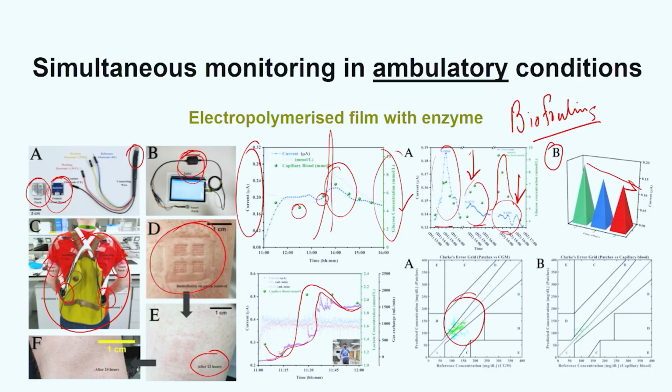The reading where you need to be very, very careful is this low value here, right? Does anybody know about the different zones between A, B, C, D and E? As you move away from zone A towards zone D, the effect of getting a false reading is much more harmful.